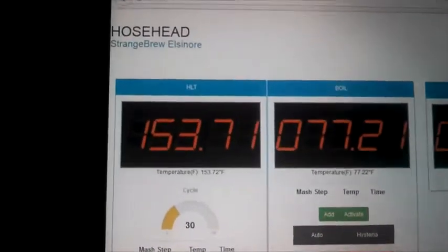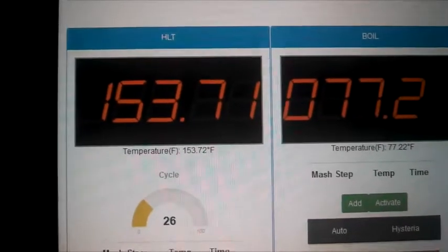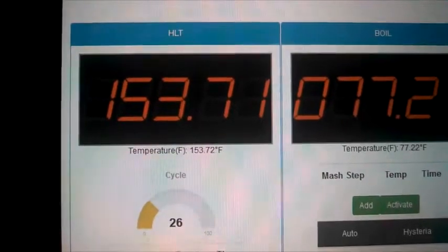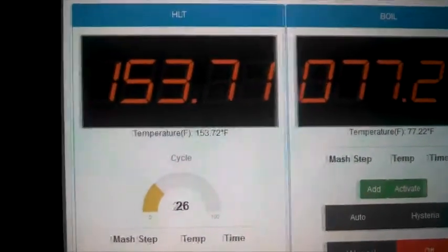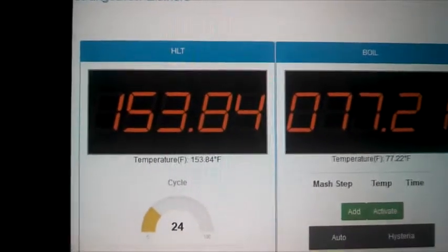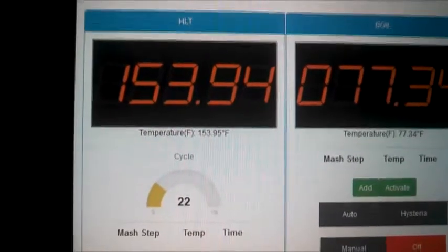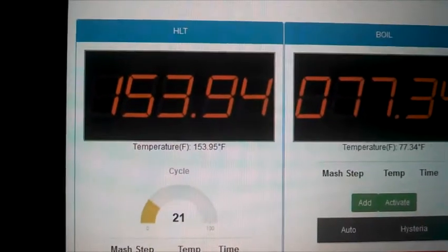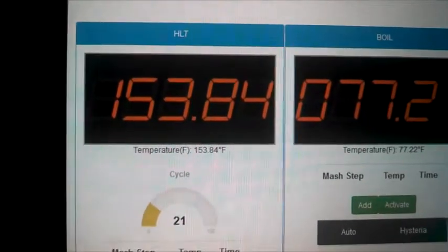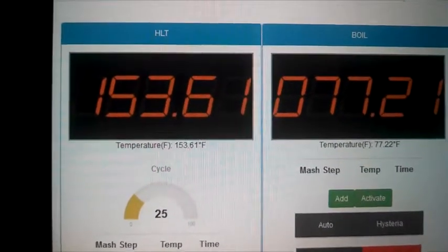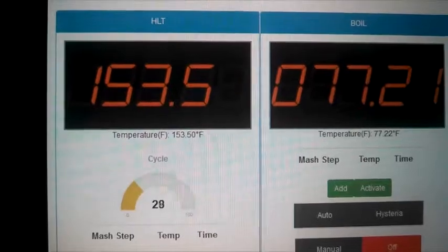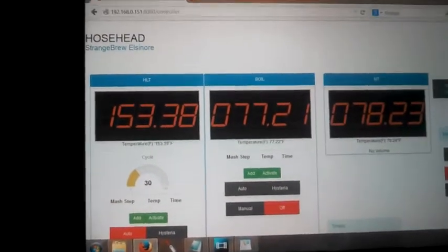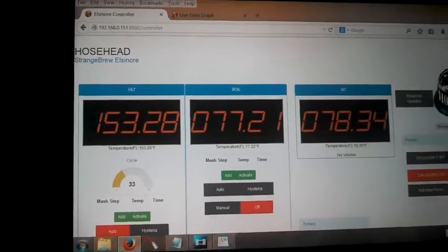All right, it's a few minutes later, and you can see that our temperature is almost to 155 degrees, which is our set point. Our duty cycle has dropped to 26%, and it's going to continue to heat that heating element at a slightly lower pace until it hits our 155 degree mark, so it doesn't overshoot. And in a couple of minutes, that will be at 155 degrees. So it fully automates the temperature control for that tank.